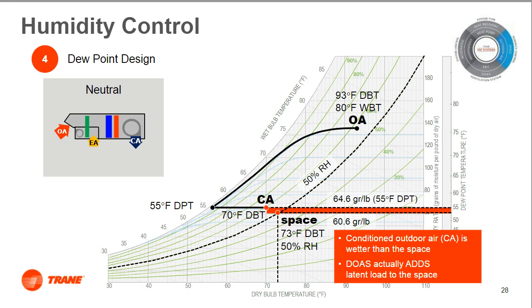Let's ask ourselves, will the 55-degree rule of thumb apply for this scenario? Well, let's take a look. As we cool down to 55, we see we cool down to a dew point temperature that is slightly higher than the dew point temperature already in the zone. When introducing the 55-degree temperature air into the space, the indoor air temp does decrease, although we're adding more moisture into the space than already present. So in this case, the neutral air delivery design would not be the desired method of providing outside air into the space.